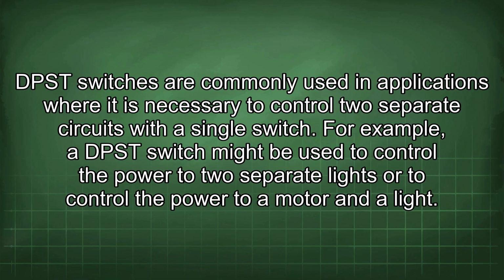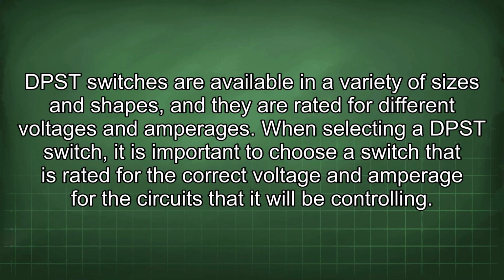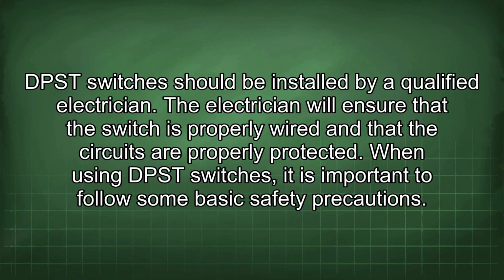For example, a DPST switch might be used to control the power to 2 separate lights or to control the power to a motor and a light. DPST switches are available in a variety of sizes and shapes, and they are rated for different voltages and amperages. When selecting a DPST switch, it is important to choose a switch that is rated for the correct voltage and amperage for the circuits that it will be controlling. DPST switches should be installed by a qualified electrician. The electrician will ensure that the switch is properly wired and that the circuits are properly protected.